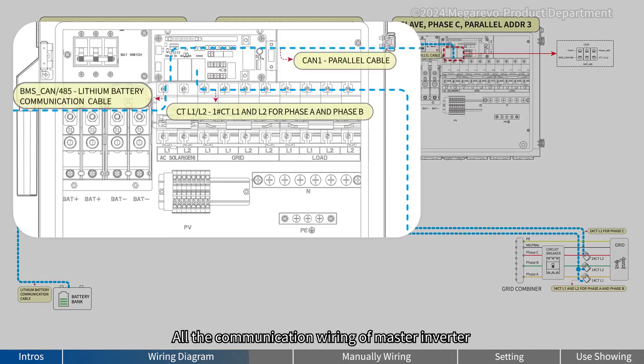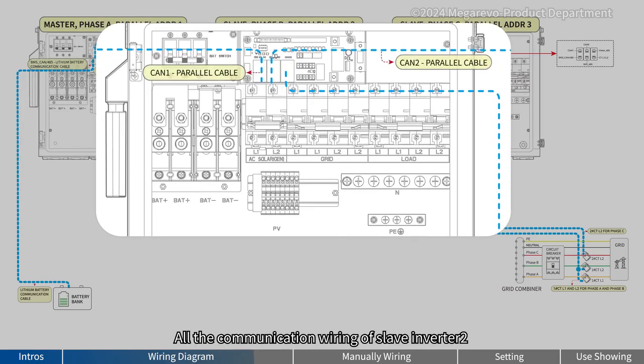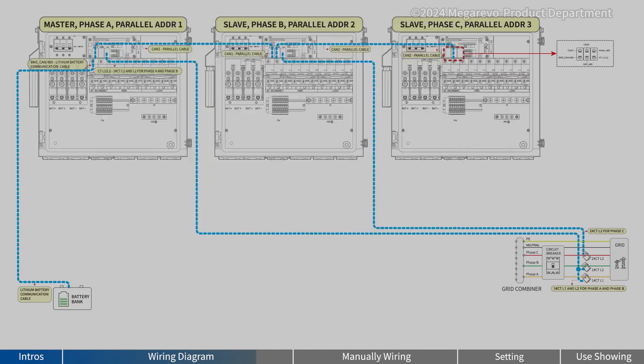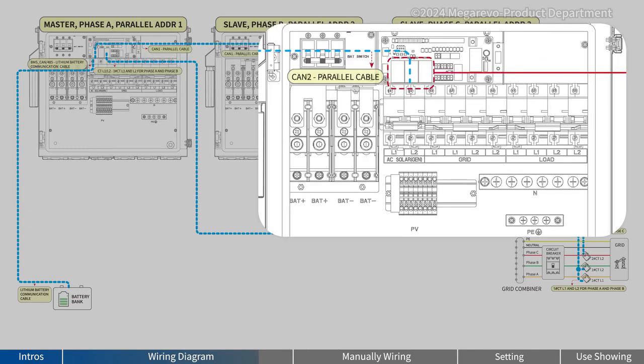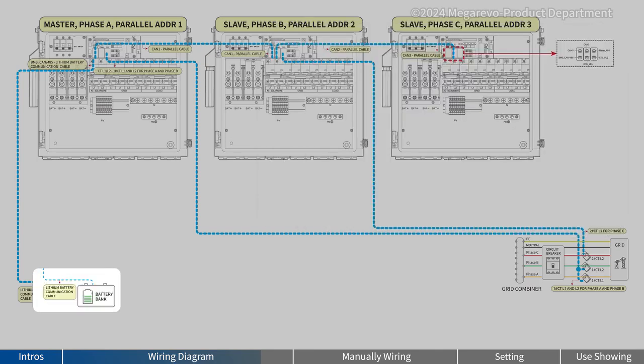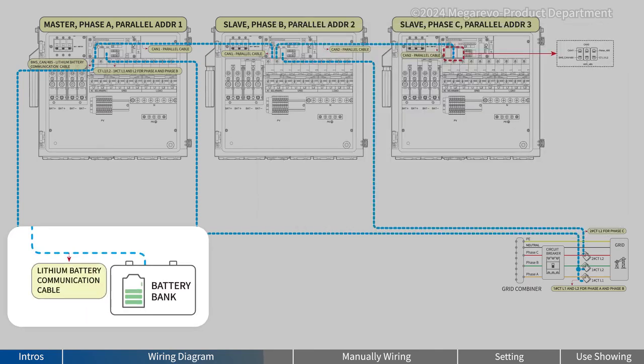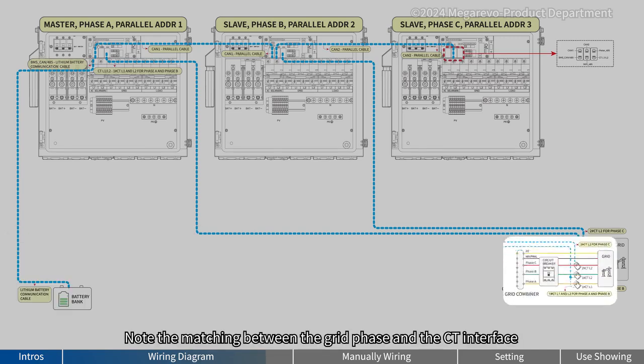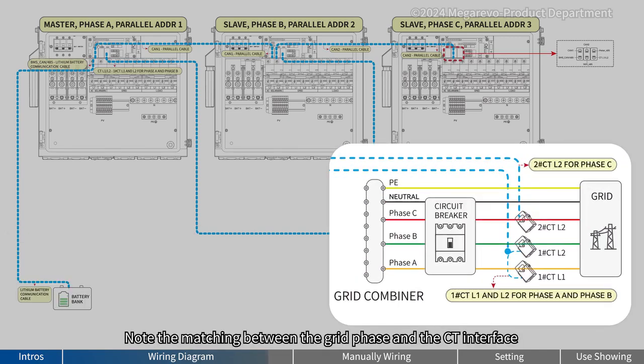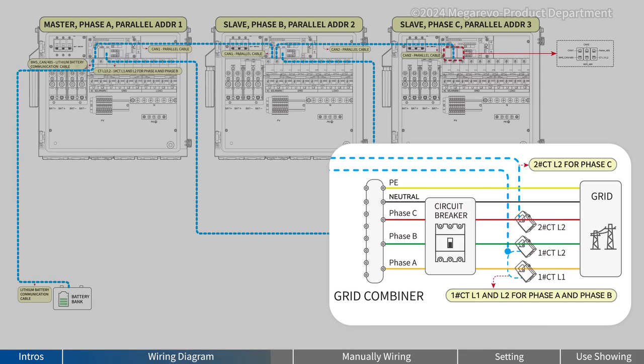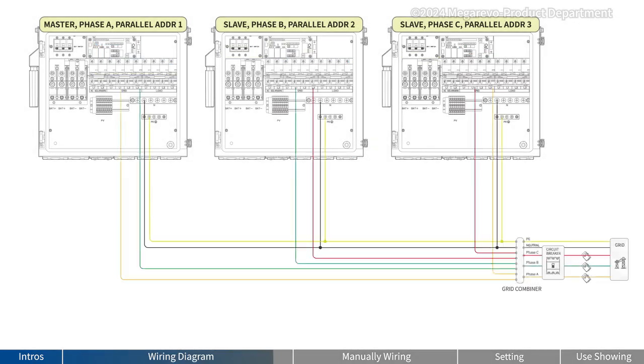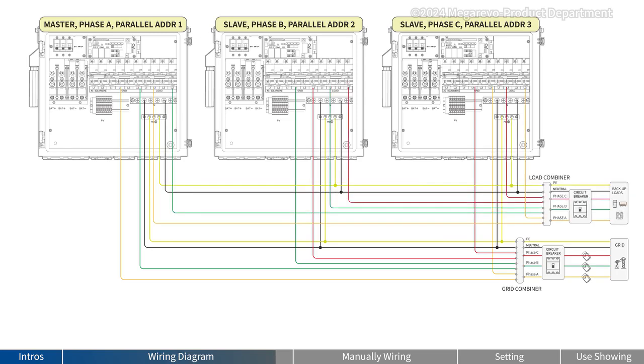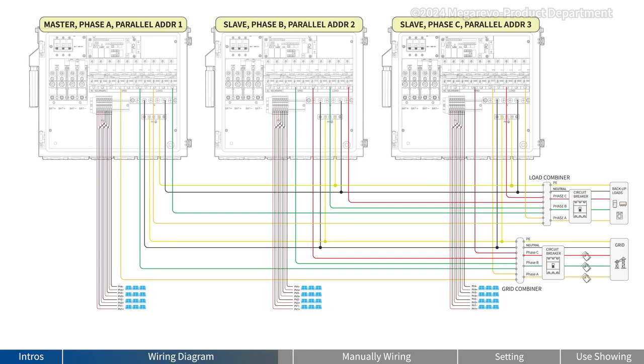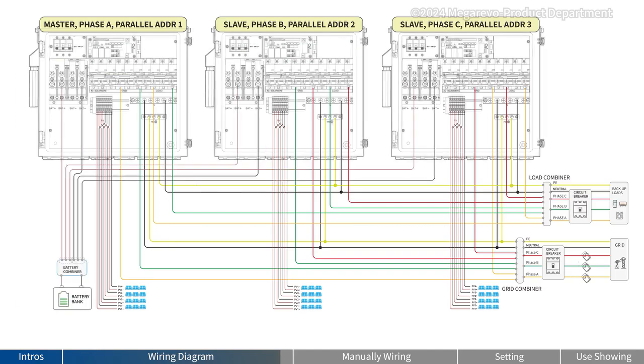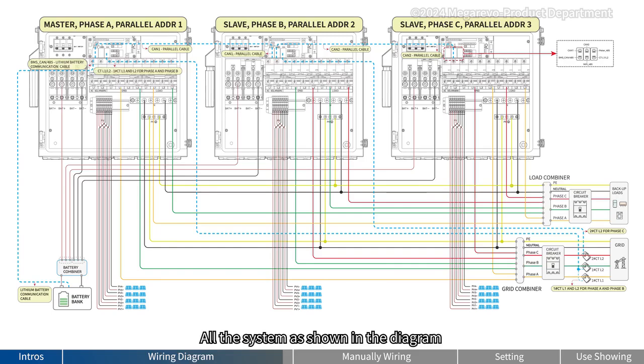All the communication wiring of Master inverter. All the communication wiring of Slave inverter 2. All the communication wiring of Slave inverter 3. Note the matching between the grid phase and the CT interface, all the system as shown in the diagram.